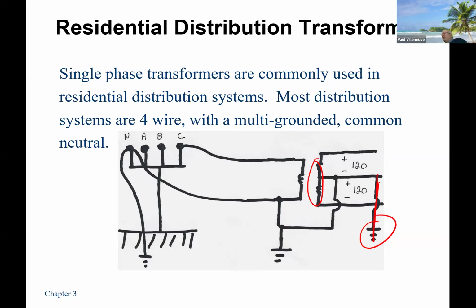Okay? That has to be connected to ground. It shows these going over here to earth ground. So for true electrical isolation, you would not want to have that connected to ground. But from an electrical safety perspective, we can't have that, right? So we have to ground everything as much as we can so that devices will have faults and then they'll be able to be detected that there's a fault that occurs. So you do have to show the grounds. But if this wasn't here, if I have a fault from here to here, no current flows through there because it's an insulator, right? It's all just flowing through the magnetics. There's no physical or electrical connection between the primary and the secondary. So there's no short that occurs.